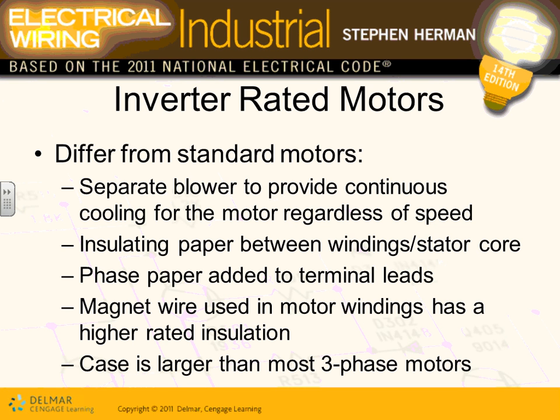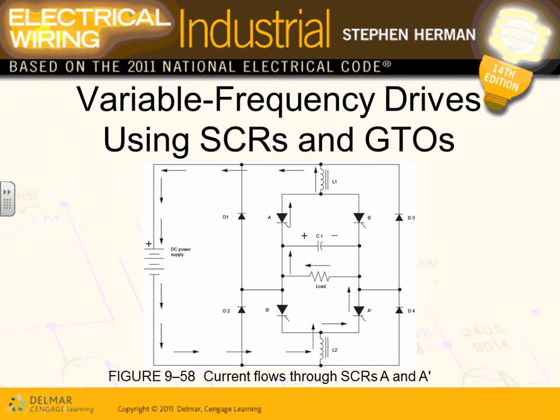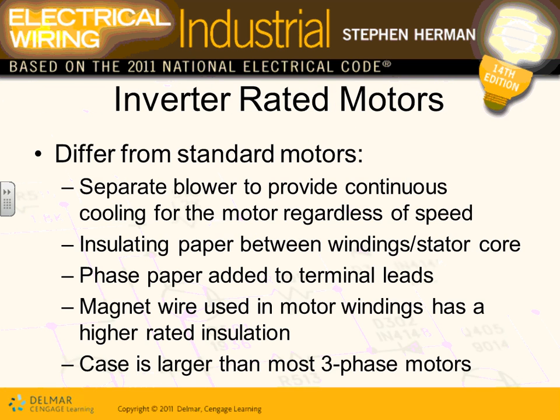So what does it do for a living? It has a separate blower to provide continuous cooling for the motor regardless of the speed. So it has some mechanism of cooling the motor because it gets hot. We have more insulating paper, guys, right here. It has more insulation between the windings and the stator core, phase paper added to the terminals, magnet wire of a better quality, more insulation, and a larger case. So as far as you're concerned, guys, it's a better built motor to handle the stress that a VFD can create on an induction motor. Sound good?